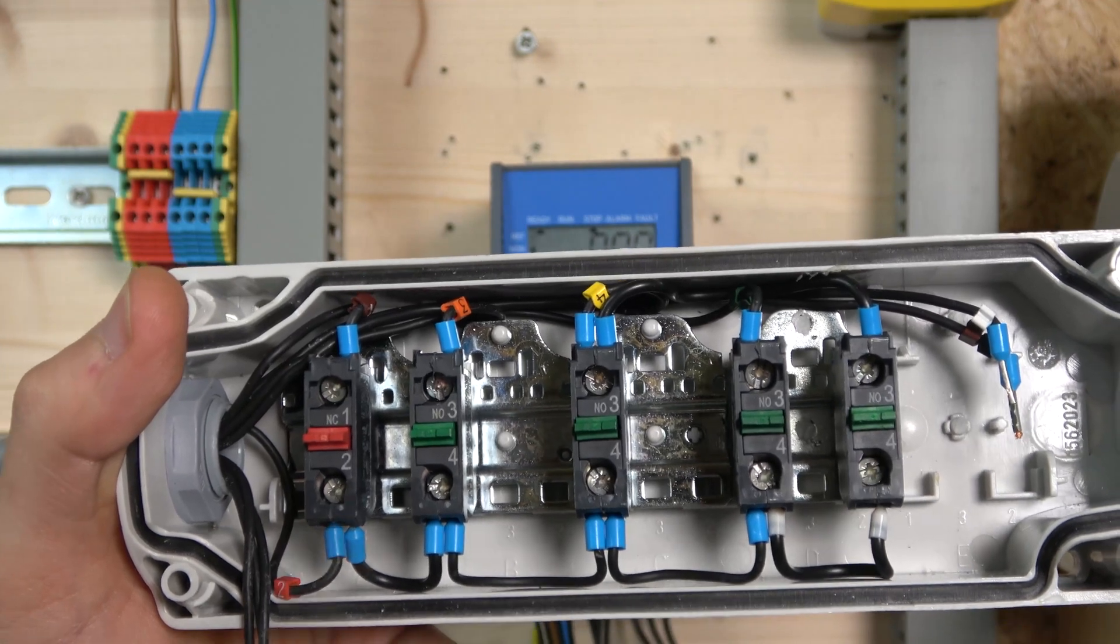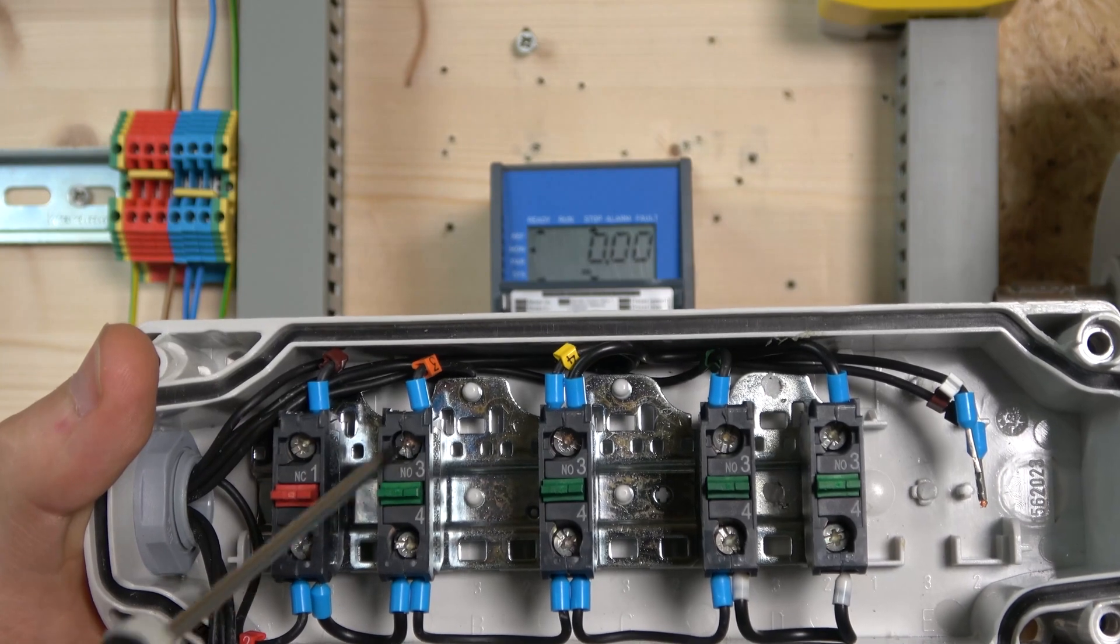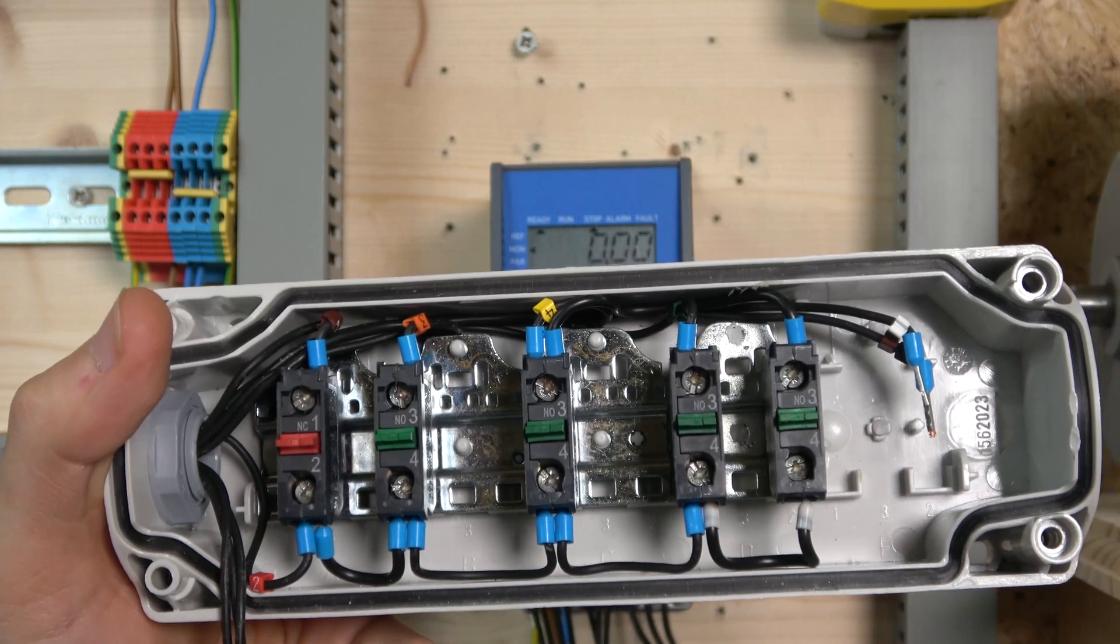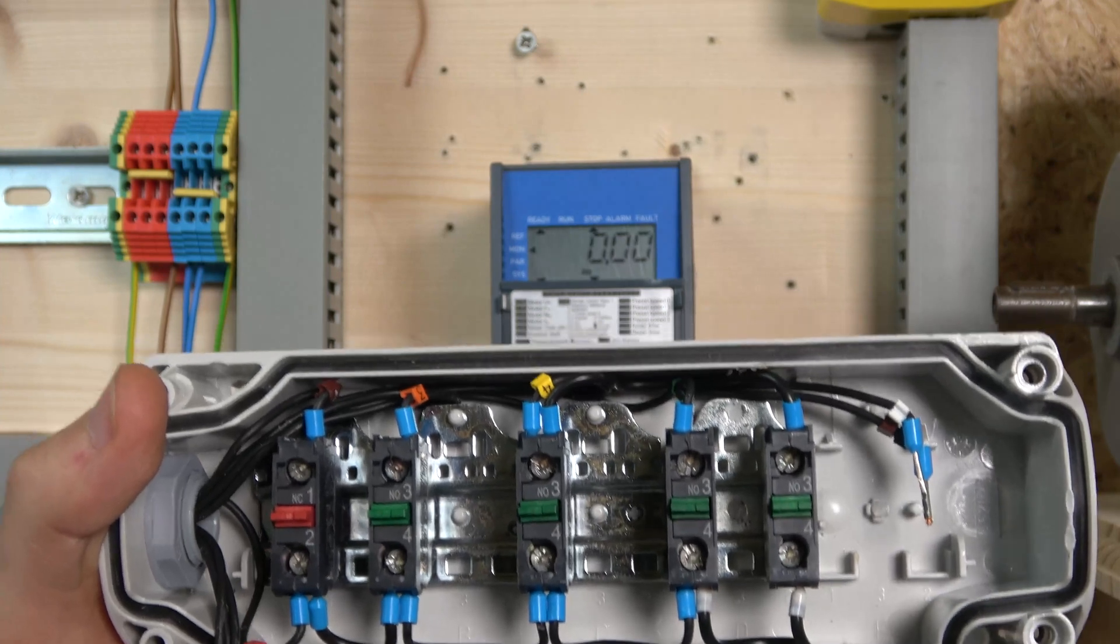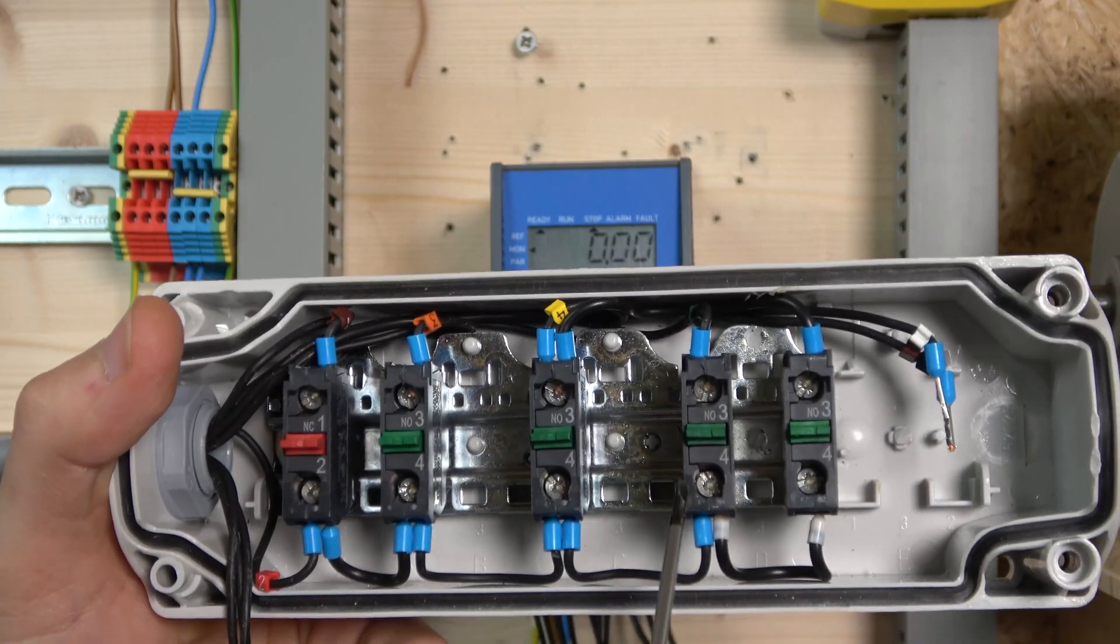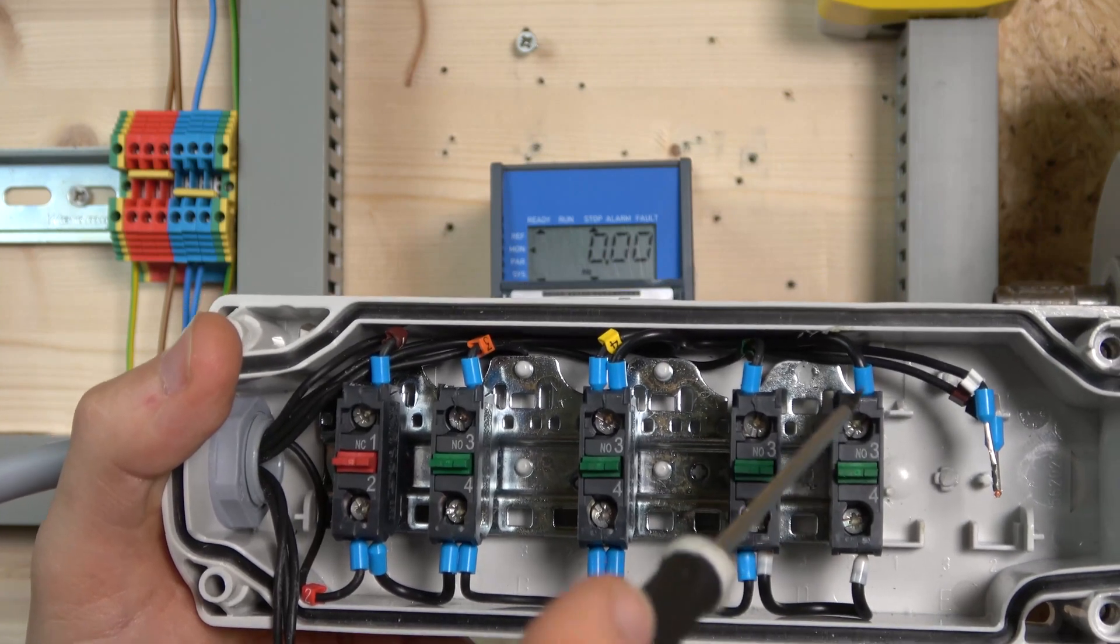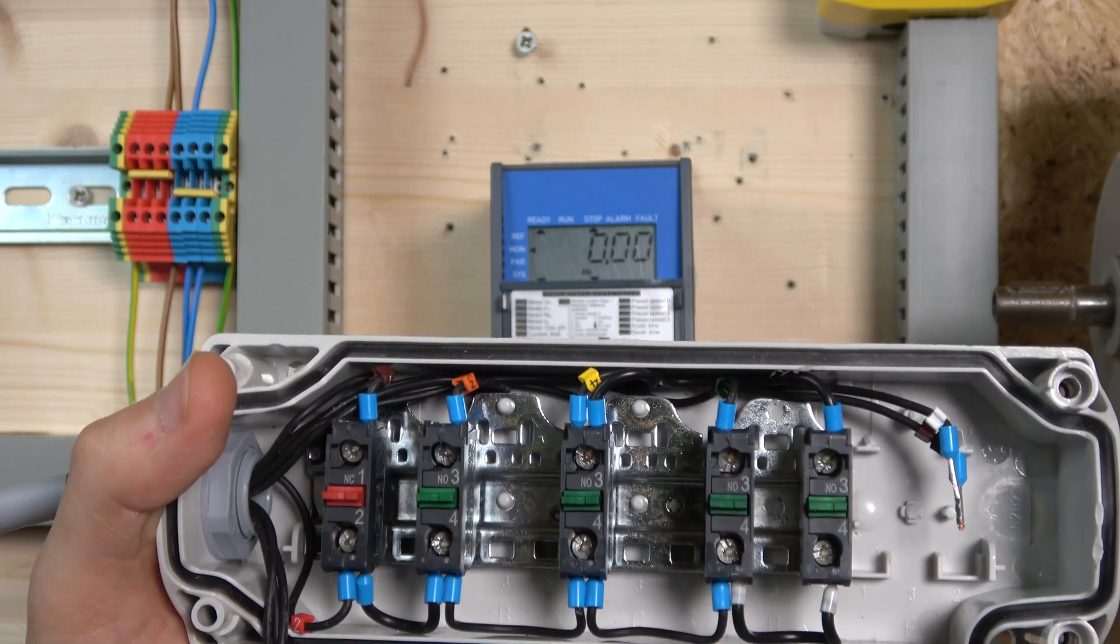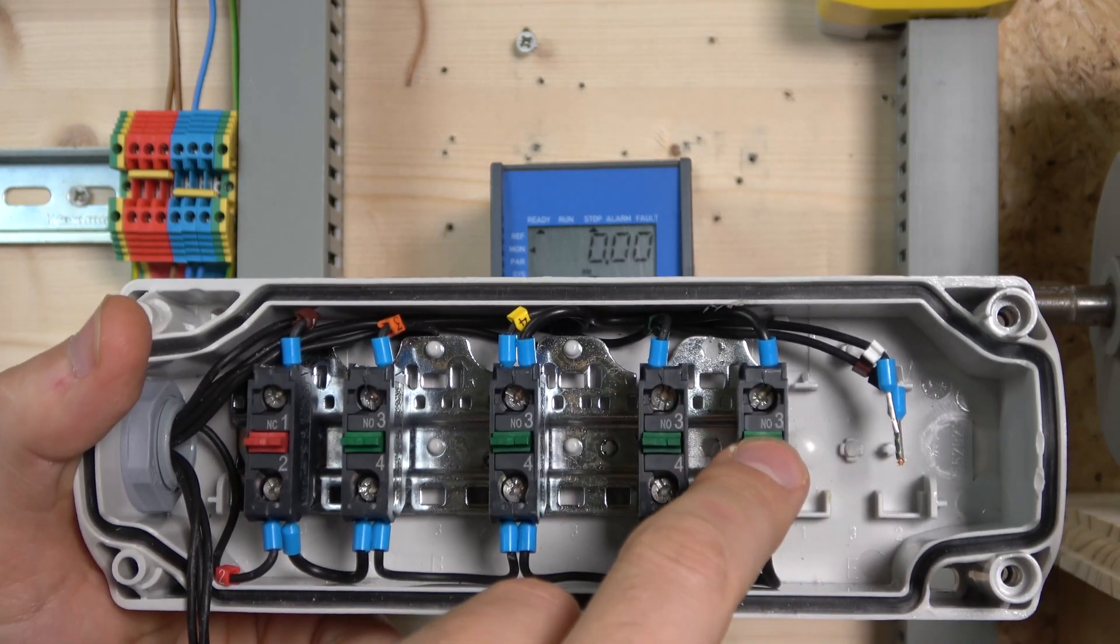The first normally open contact runs forward, second is reverse, and these two activate jog. There's no actual jog function in the drive itself - at least I couldn't find it. We'll use one of the preset speeds as our jog. For preset speed to work, it requires a run signal, which can be reverse or forward. I chose reverse.